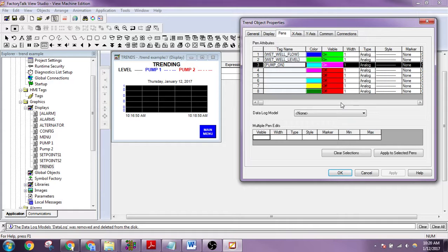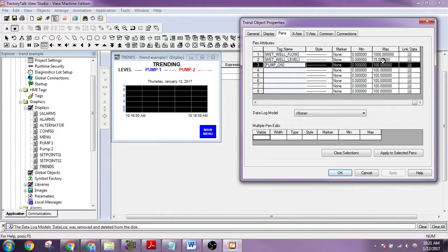And what gives? You look through the logic and stuff like that, and what I've found is a lot of people can deal with the logic of a process or a machine, but typically only programmers dig into the screen, so they don't know that much, and he might not know to look for this min and max.